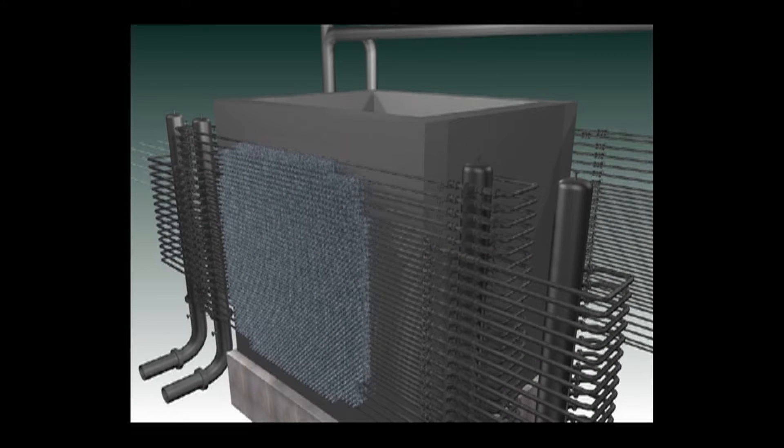Nozzles are then attached to the outside shield faces and the process tubes are sealed to the inner diameter of the nozzles. A small tube called a pigtail connects the cross-header to each nozzle. The water flow for each process tube can now flow from the riser to cross-header to nozzle and into the process tube.